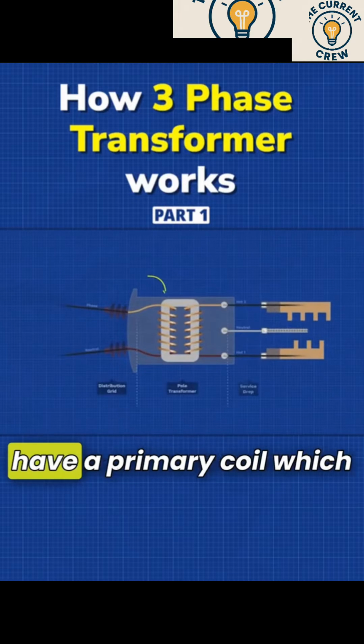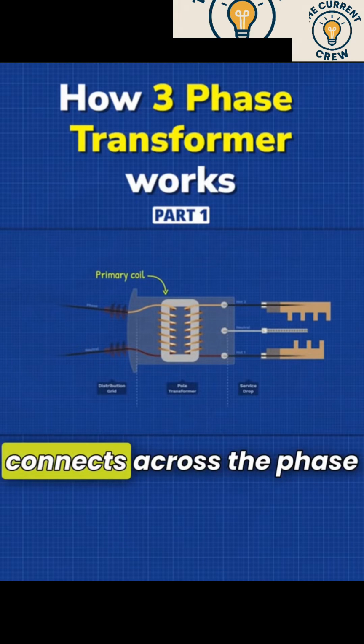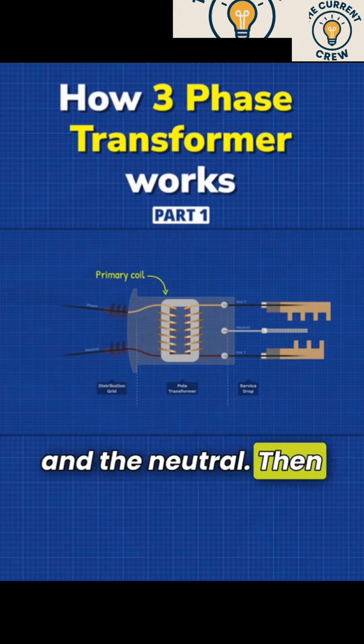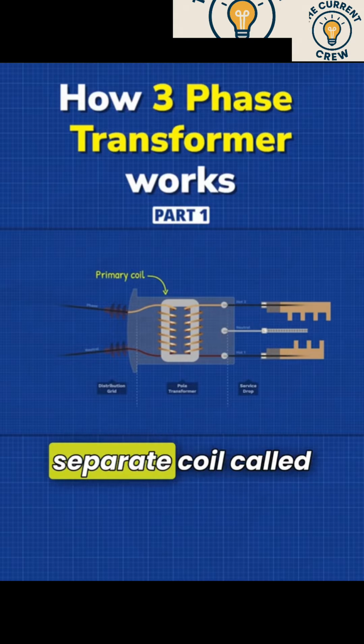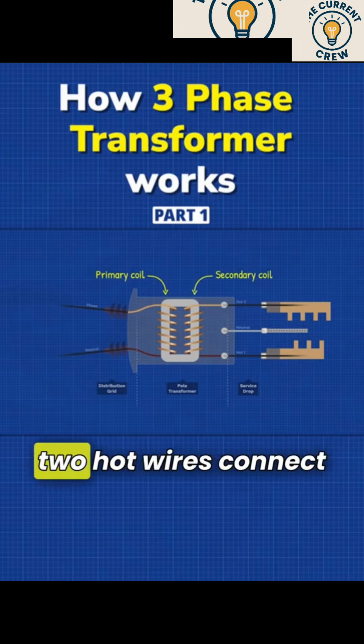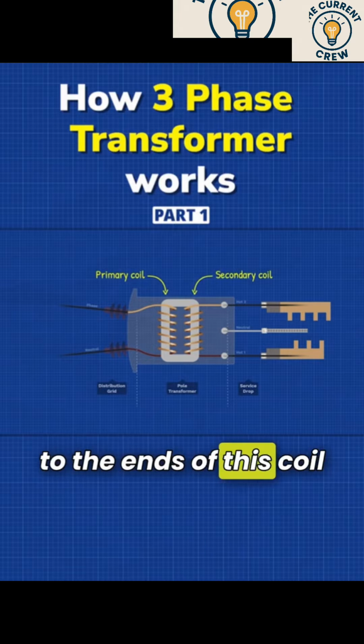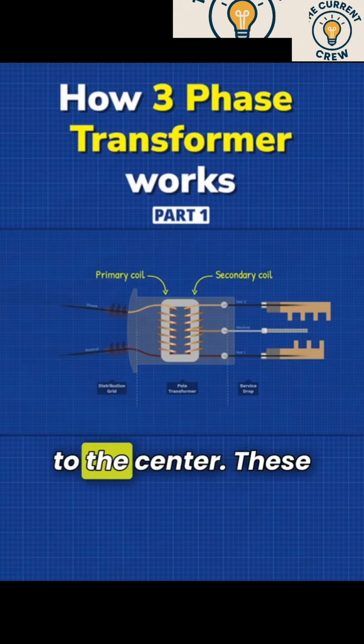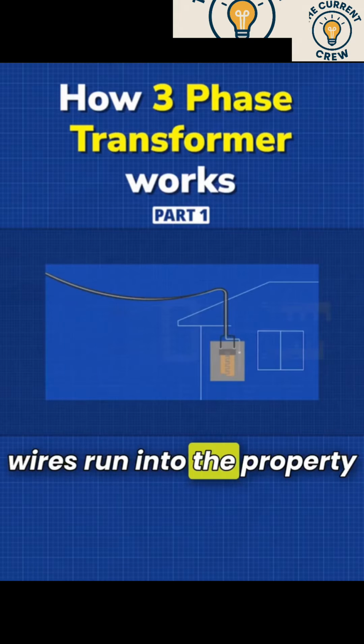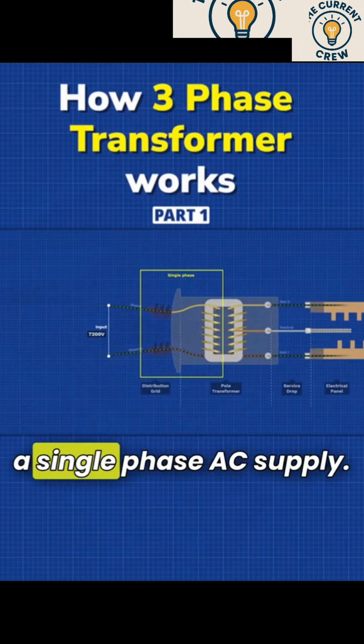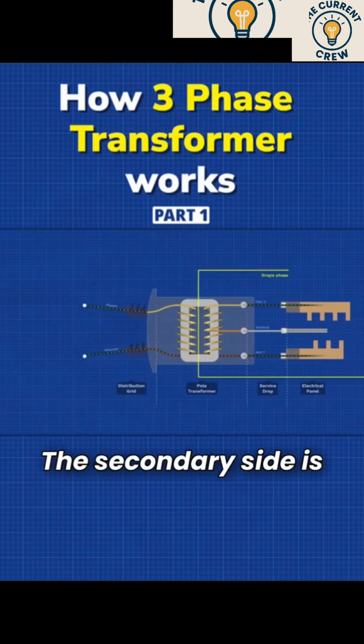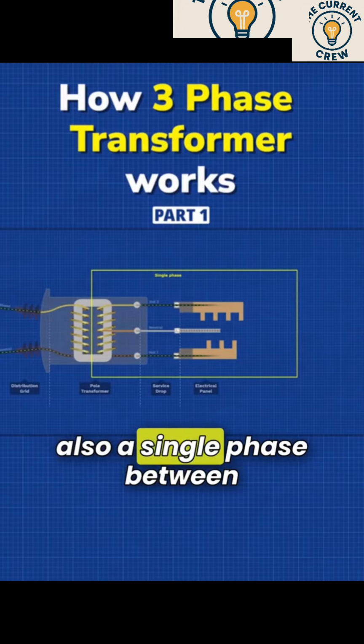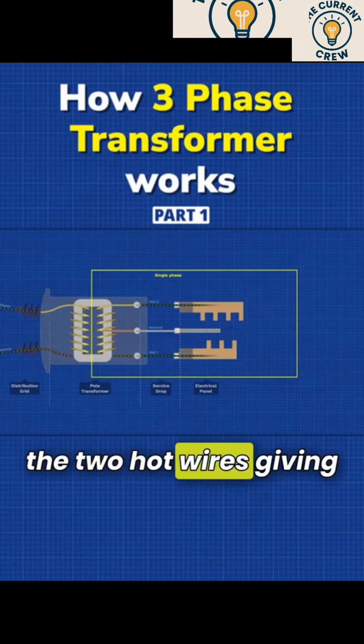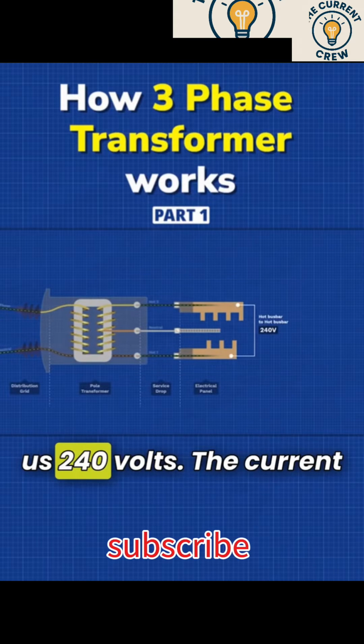Inside, we basically have a primary coil which connects across the phase and the neutral. Then we have another completely separate coil called a secondary, and the 2 hot wires connect to the ends of this coil and the neutral connects to the center. These wires run into the property to your electrical panel. The primary side has a single phase AC supply. The secondary side is also a single phase between the 2 hot wires, giving us 240 volts.